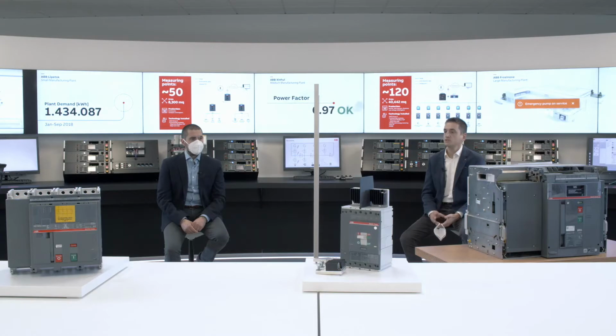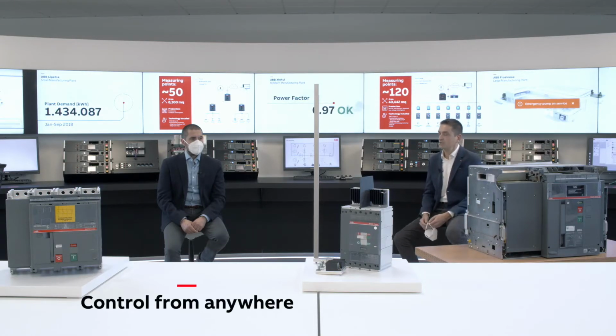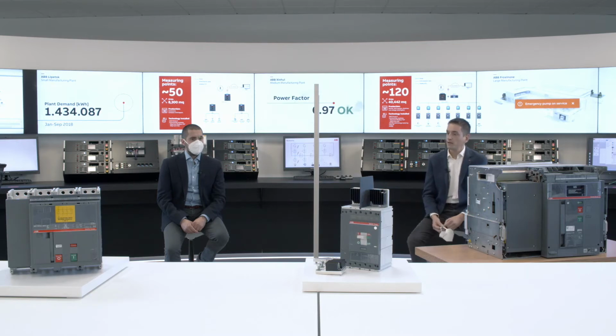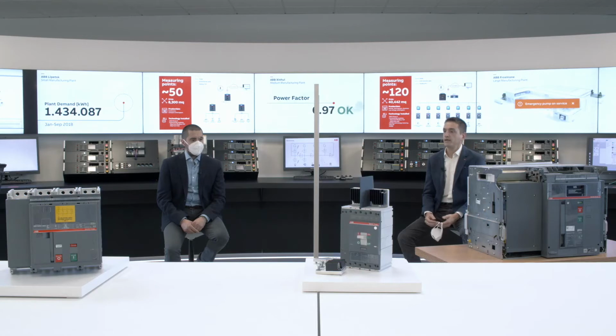But withstand current and breaking capacity are not the only parameters we have to consider when we choose a circuit breaker or a switch based on circuit breakers. We can also consider items like remote controls. With our circuit breakers and MCCBs, we can use accessories like shunt trips and undervoltage release. Very common and well-known accessories we can find in our breaker offer to have full remote control of our breaker or switch. In other words, we can have the same remote control and the same nominal voltage we find in all the control circuits.